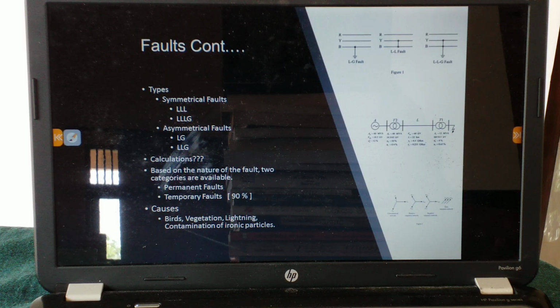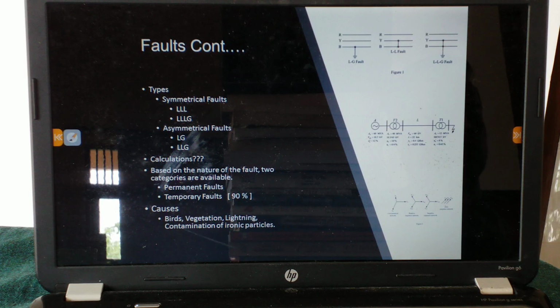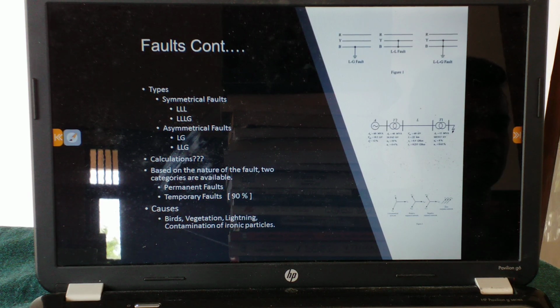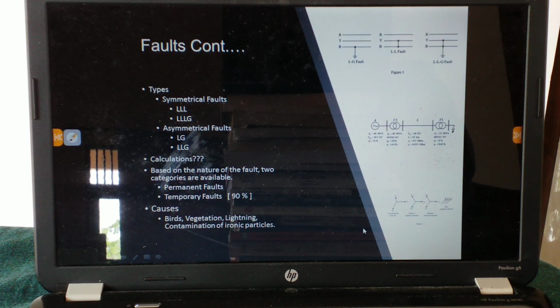There are two types of faults: symmetrical and asymmetrical. A symmetrical fault has no intention to disturb the symmetry of the system. In generators, we generate electricity having three phases, each phase having the same load. We transmit in the same manner, keeping symmetry, loads are the same. In a fault too, it keeps that same manner. That means all three phases feed the fault symmetrically. If one phase feeds 10 amperes to the fault, the other two phases also contribute the same amount.